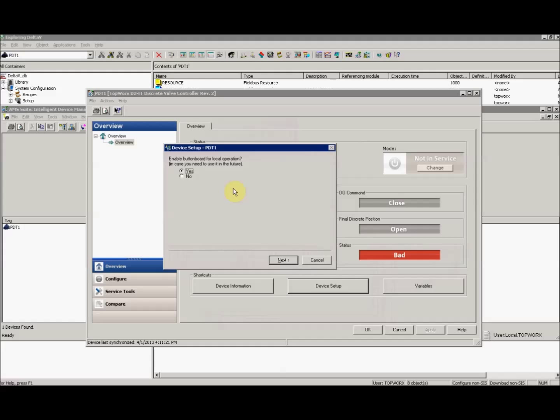Now it's asking us if we want to enable the button board for local operation. I'll select Yes. Once again, just a reminder, this will only enable the button board for use when the resource and transducer block are out of service. This way no one can pop the lid in the field and change settings in the device. We'll hit Next.